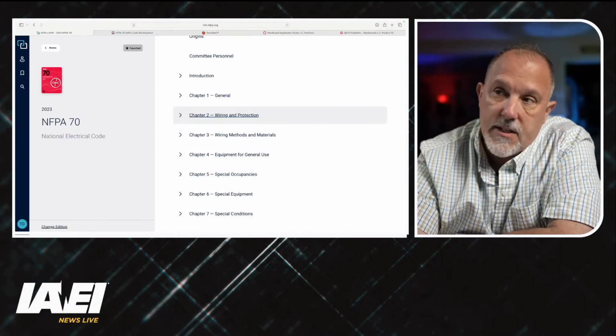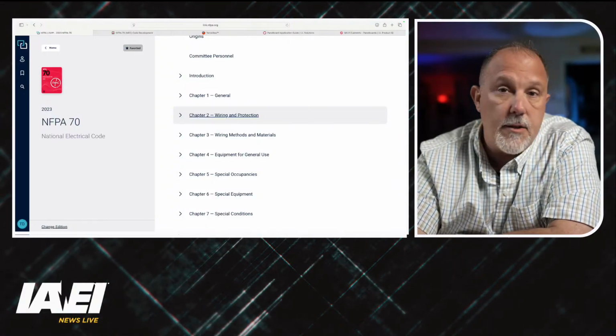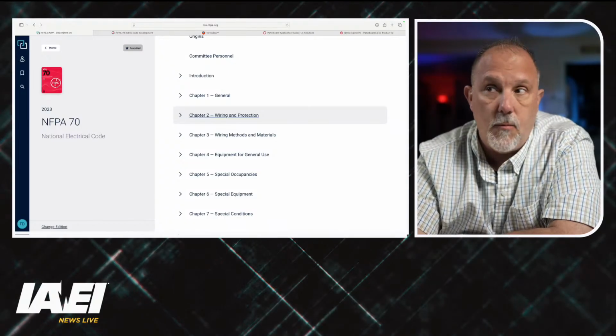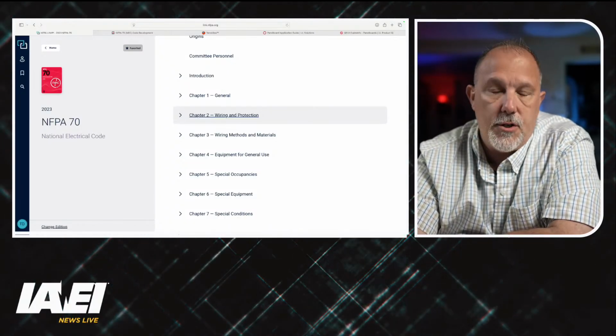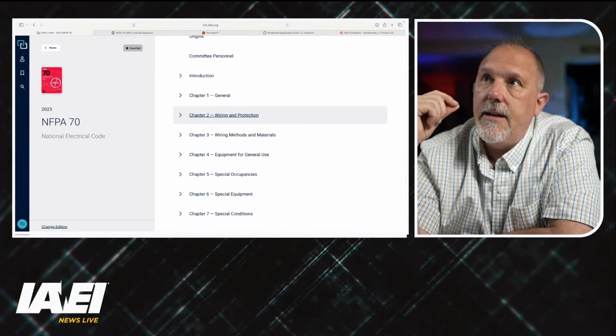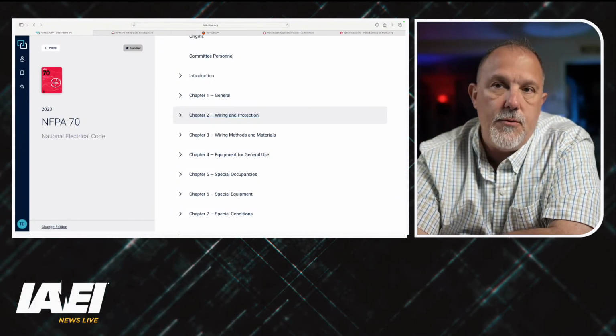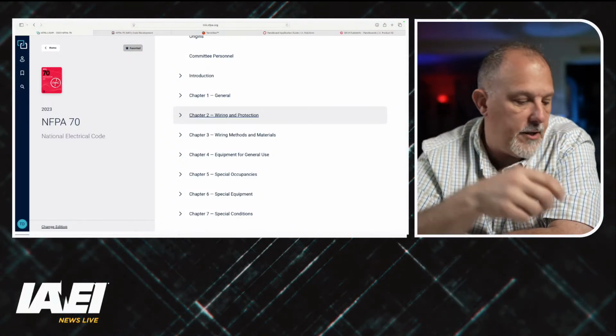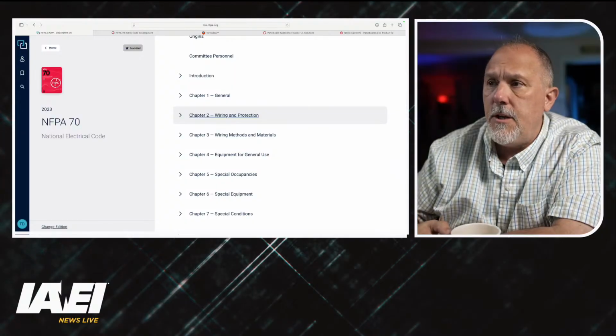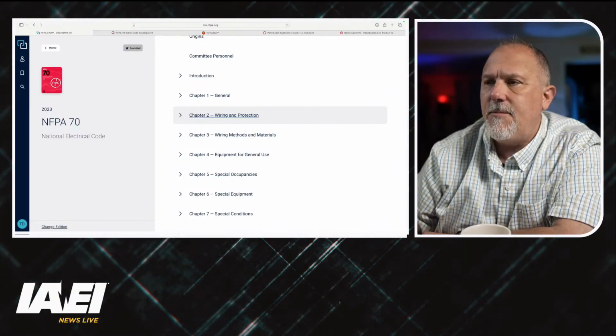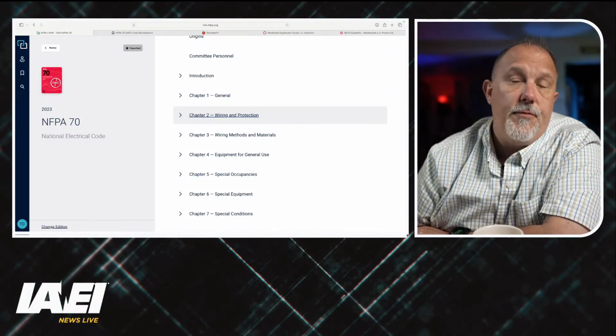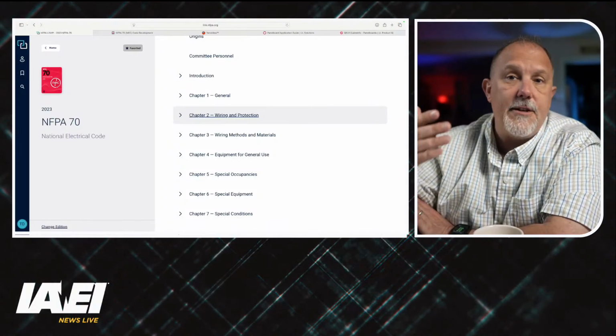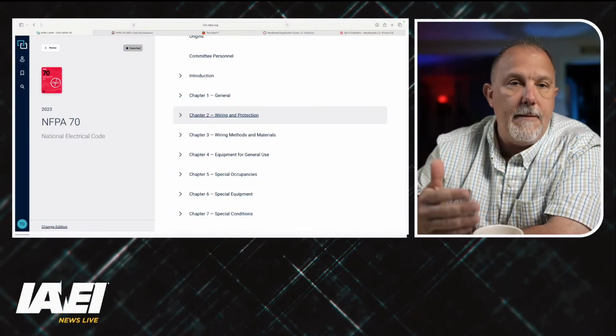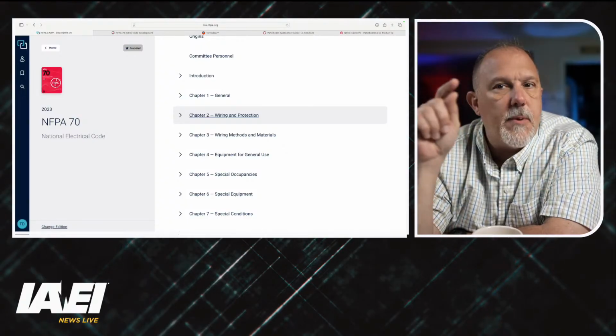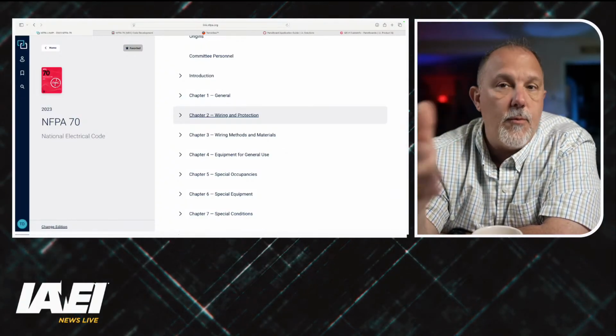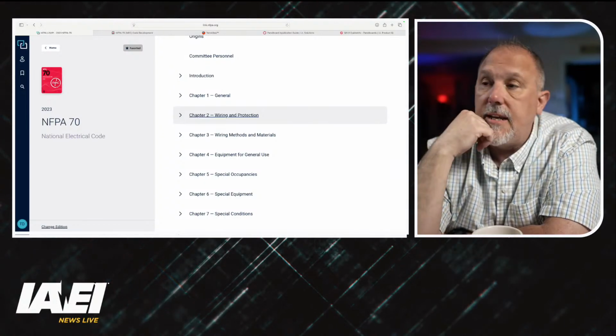If I think about the way the code is laid out, you have your general requirements in Chapter 1. So there might be requirements for panel boards in Chapter 1, wiring and protection in Chapter 2. It is likely that in Chapter 2 you have some requirements that impact the panel board because you want to protect the panel board itself. Chapter 3 is wiring methods and materials. There probably are requirements in Chapter 3 because you're going to land and route wires. You're going to bring a wire into that panel board. It's probably going to use a raceway of some sort, and it will be wire. So Chapter 3 is probably going to impact a panel board.